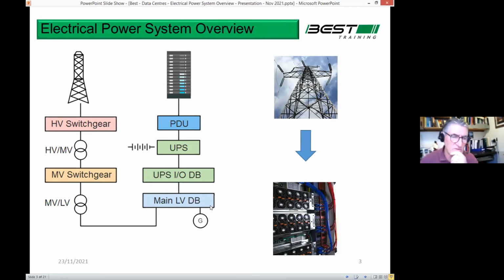But there's also a UPS system. Now, the UPS is a battery backup system. It stands for uninterruptible power supply. It basically is a battery backup system that provides a no-break backup to the power system. So if the power fails, the UPS continues to deliver power without even a microsecond of a break. It just continues to feed power to the essential load, which is, of course, the servers.